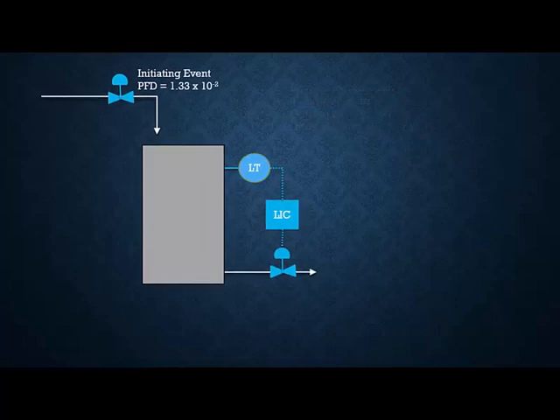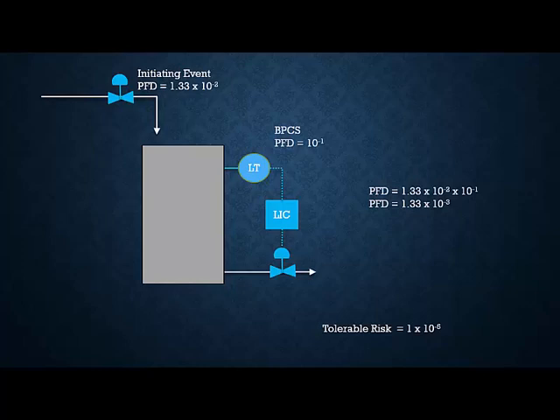So in LOPA, you look at protection layers of what else can prevent that fatality from occurring. The next layer would be the BPCS system, a level transmitter, a level controller, a control valve. So tank level gets high, control valve opens, tank level goes down. Everything's good, right? But not quite because the BPCS should work, but nothing works 100% of the time. So a BPCS typically has a probability of failure on demand of 0.1. So if its probability of failing is 0.1 and the initiating event is 1.33 times 10 to the negative 2, you multiply them together and the odds of them both failing is 1.33 times 10 to the negative 3. Better, but still not tolerable. You still have too much risk with this situation, so you need another layer of protection.